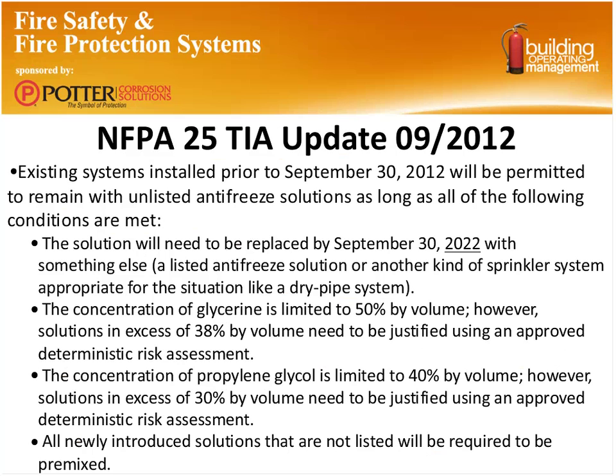Most recently, the NFPA did issue a TIA for NFPA 25, and this is a very current one, issued in September of 2012. And what we see in this one is that they've kind of backed off a little bit and said, okay, we know that these systems exist, but we also agree that freeze protecting these systems is important, because if they're frozen, they're of no value to anyone, because they definitely will not discharge and put a fire out. So by September 30th of 2022, all systems are supposed to be either replaced with a dry pipe system or changed out and have the listed antifreeze premixes put in.